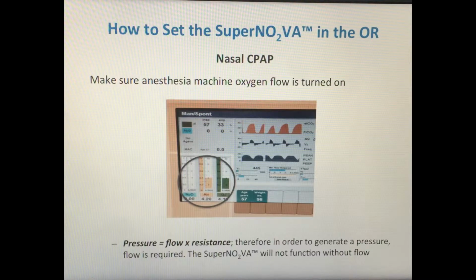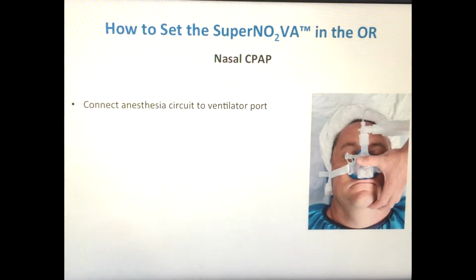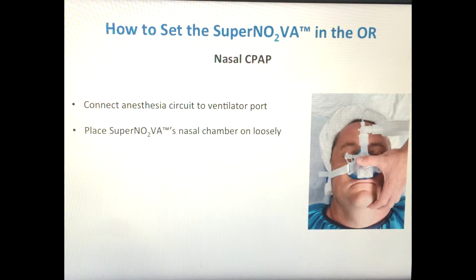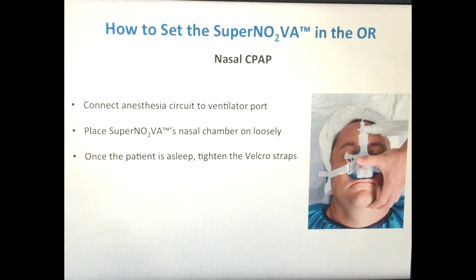The reason why this is important is if we remember, pressure equals flow times resistance. In order for us to generate a positive pressure, which is what we want to do, we need oxygen to be flowing. Without oxygen, the supernova will not function properly. Next, we want to connect the supernova to the anesthesia port, as shown here in the picture. After that, we want to place the supernova on loosely so that it's comfortable for the patient while the patient's still awake. However, once the patient goes off to sleep, we then want to tighten the Velcro straps so that it creates a nice tight seal around the patient's nose.